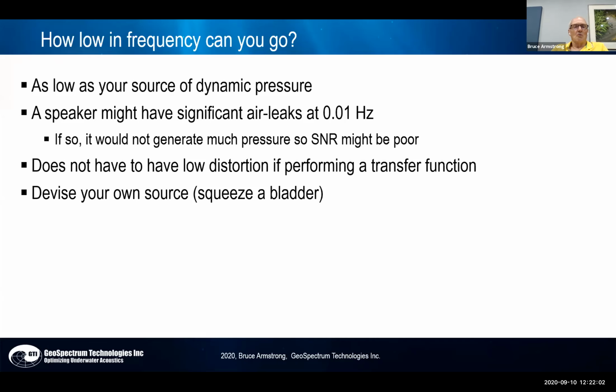Another question was, how low a frequency can you go? And the answer is as low as your source of dynamic pressure. Now, if you're using a speaker for your source of pressure, I don't know if speakers are airtight at 0.01 hertz, for example. If you've got an air leak that's significant over your 100-second period, then you wouldn't get much pressure out of your speaker. But the neat thing is, you don't have to have a low distortion source if you're producing a transfer function. So if you had a sealed container, you could just take a bladder and squeeze it by hand, and you would create a complex spectrum that your spectrum analyzer would sort out for you, and you'd still get your accurate calibration down to whatever frequency you choose to use it at.